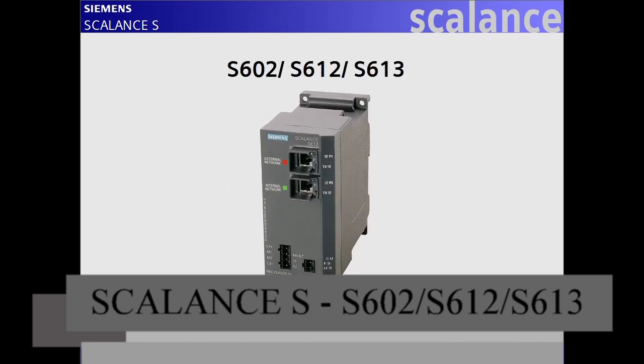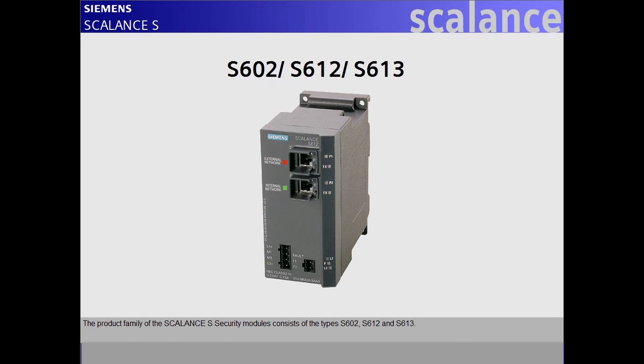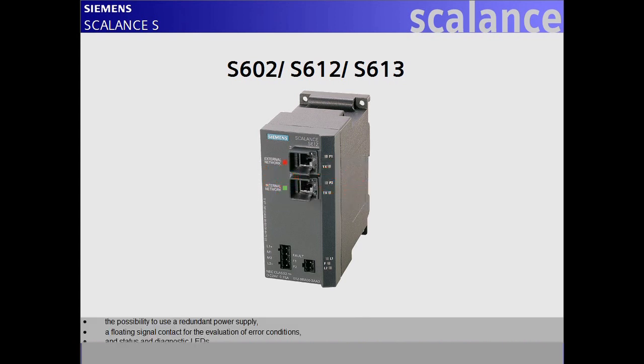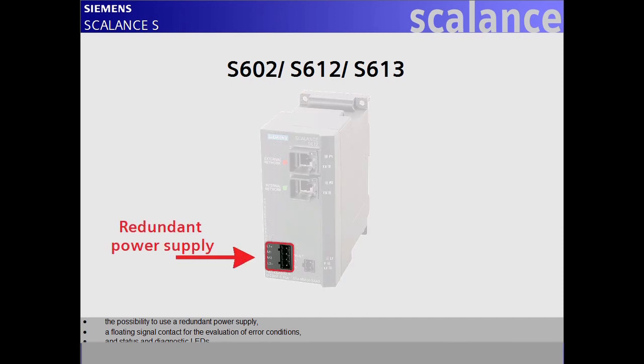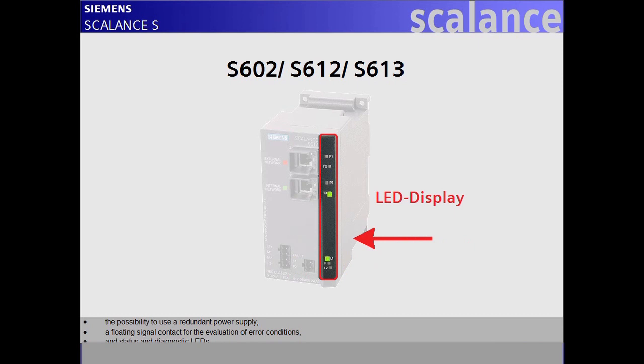The product family of the Scalance S security modules consists of the types S602, S612, and S613. The mechanical housing design is comparable to that of the X100 and X200 switches — a rugged industrial-use housing in S7300 design with degree of protection IP30, allowing flexible installation and high temperature ranges. Additional features include a redundant power supply option, a floating signal contact for error condition evaluation, and status and diagnostic LEDs.